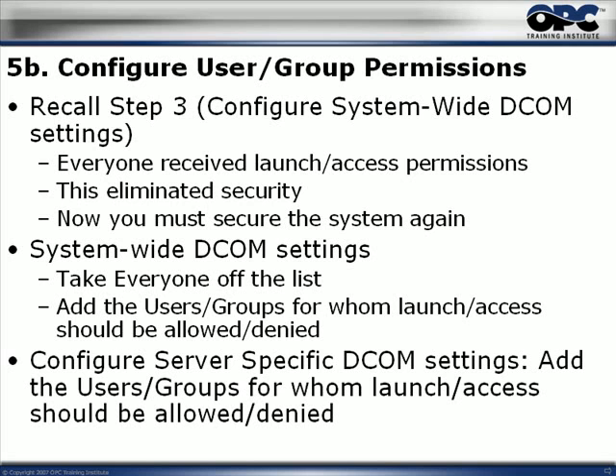Second, we're going to configure the user and group permissions. Remember that in step number three, when we configured the system-wide DCOM settings, we gave access to everyone — we gave them access to launch and to access all the applications. Now we have to take that back, because where is the security if everybody is allowed to launch, start, and access our data? It's not there. So go back into the system-wide DCOM settings, take everyone off the list, and add the specific users and groups that should actually get the launch and access permissions.